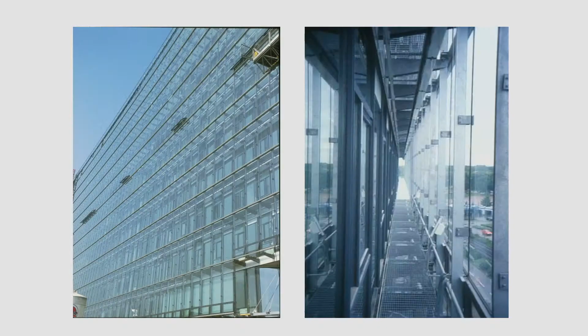The first problem: the trees died—pretty expensive trees from Argentina. The reason was a signal during Christmas break caused the smoke exhaust openings from the atria to open, nobody noticed, and temperatures in the atria fell below freezing, so the trees died. Some recovered, but it was a typical control issue.